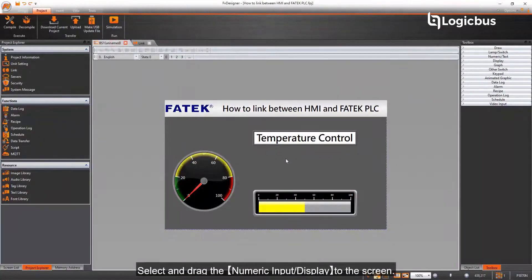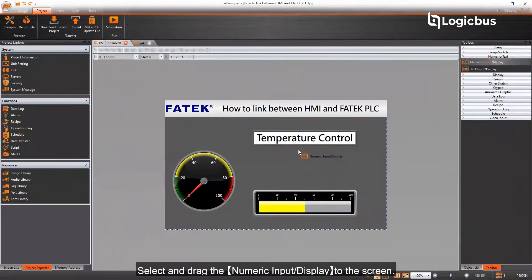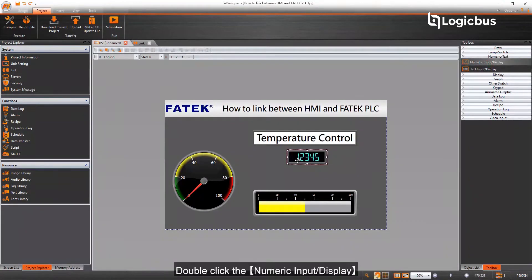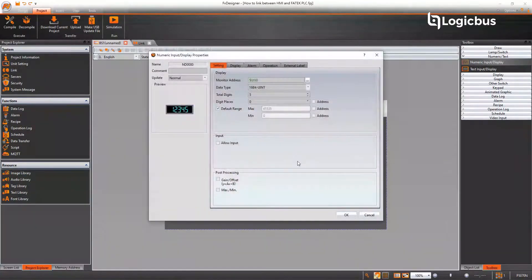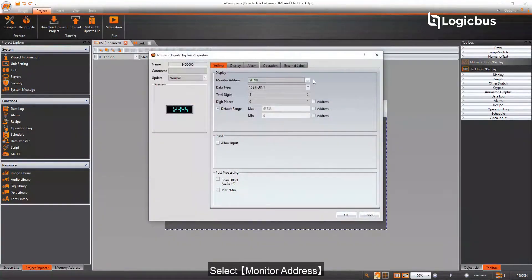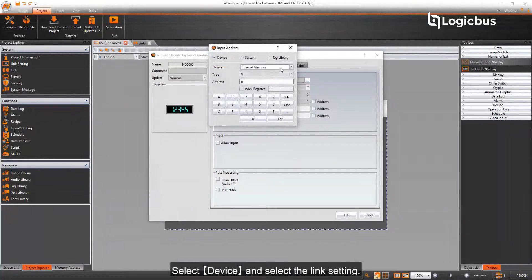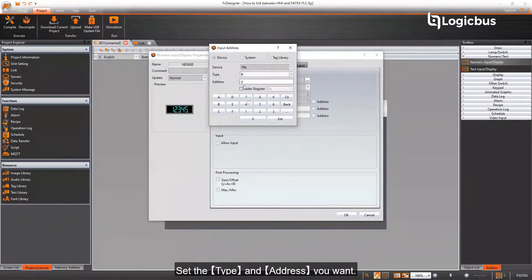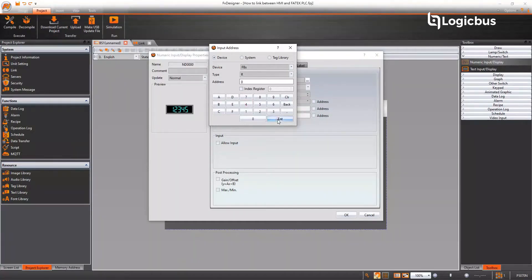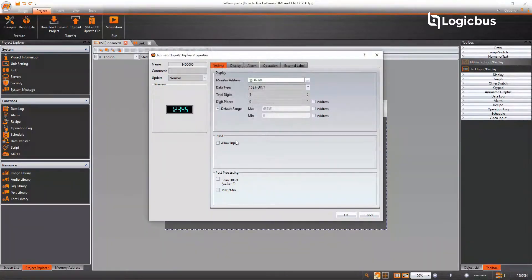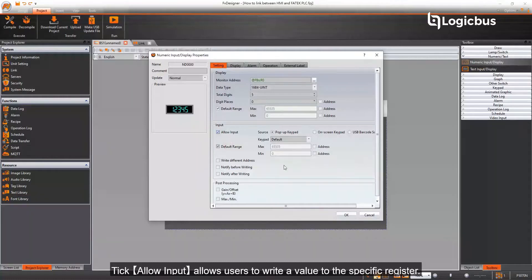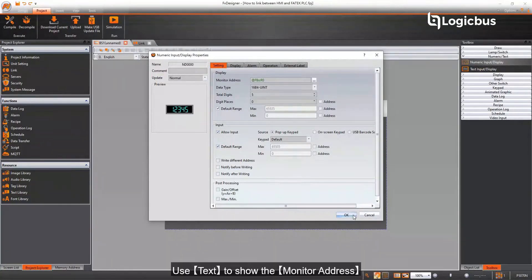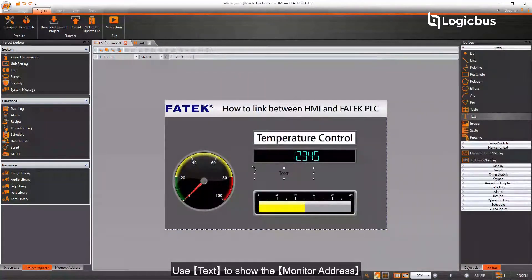Select and drag the numeric input display to the screen, then double-click it. Select Monitor Address, then select Device and select the link setting. Set the type and address you want. Tick Allow Input to allow users to write a value to the specific register. Use text to show the monitor address.